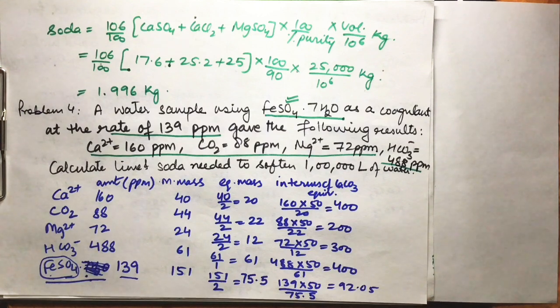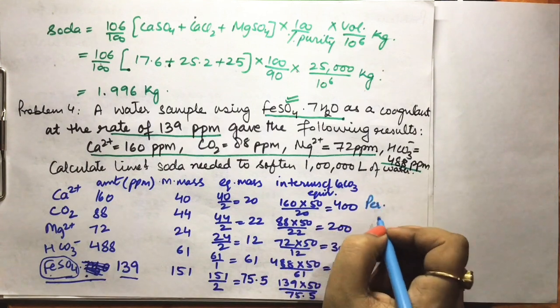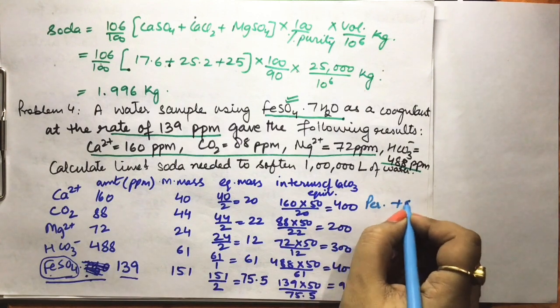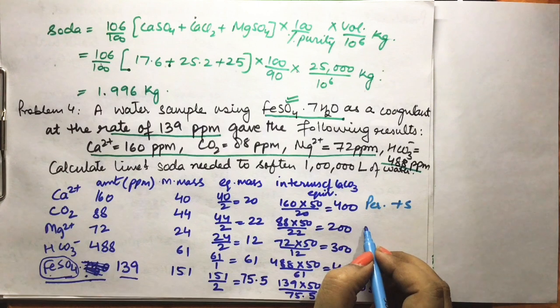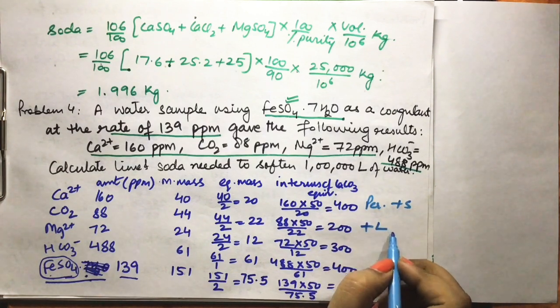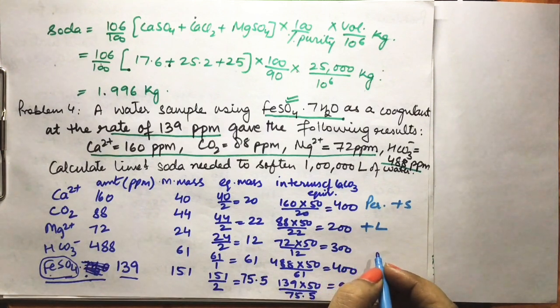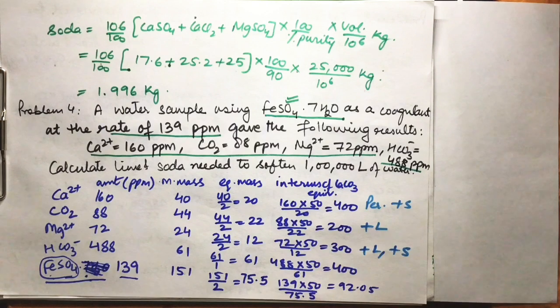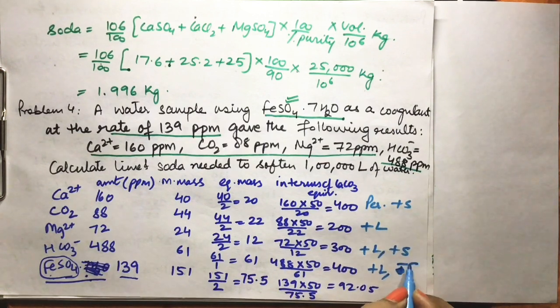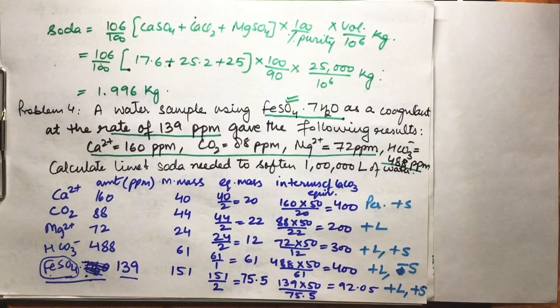Now identify lime and soda: Ca²⁺ alone is permanent hardness of calcium — removed by soda. Bicarbonate goes in lime and is subtracted in soda. FeSO4 is permanent hardness of iron — goes in both lime and soda. Magnesium permanent hardness also needs lime and soda.